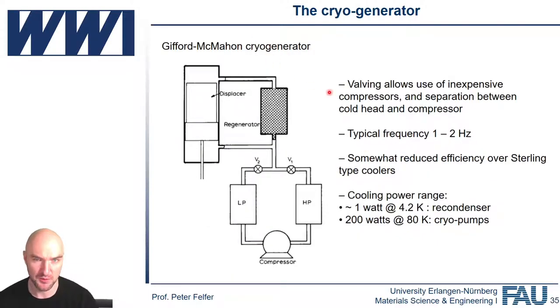So the cryo generators that we use are Gifford-McMahon cryo heads, and you know the typical sound when you go into an atom probe, the tick, tick, tick, tick. That's actually the sound of the displacer and the regenerator of the cryostat switching over, as you can see with the two valves here. Essentially, what they do is they compress helium, take the heat out of the helium, move the compressed helium into the cycle, and then you expand the compressed helium. Most of the cryostats that we use in atom probe are two-stage cryostats, so you don't only have one stage, but you have two cooling stages here.